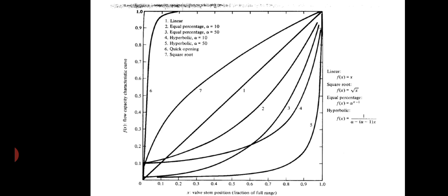control valve, right? So basically in the quick opening valve, we are supplying a small amount of pressure, and corresponding to that pressure, the plug produces a very large increase in flow for a small initial change in stem travel, right? So these are the concepts for the quick opening valve. However, the equal percentage is the characteristic most commonly used in process control.